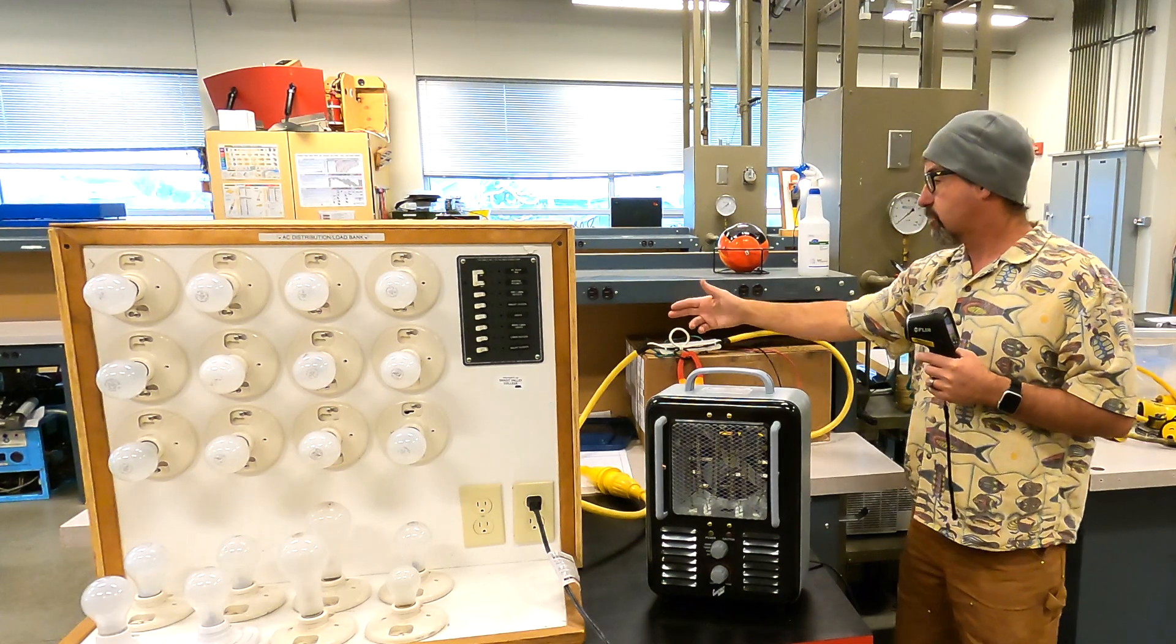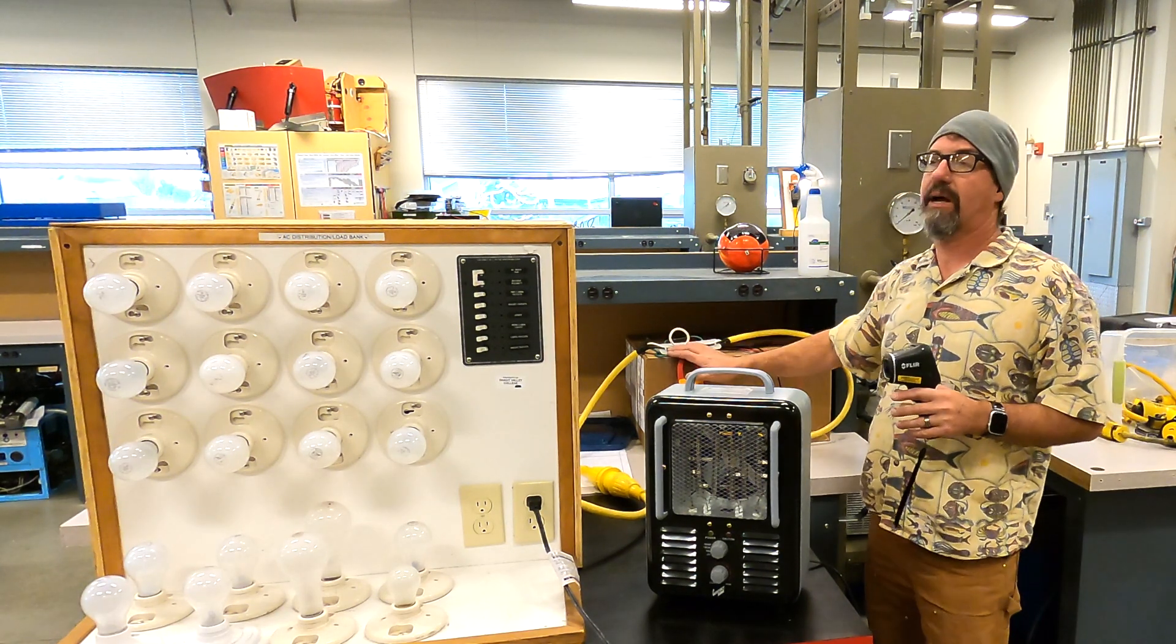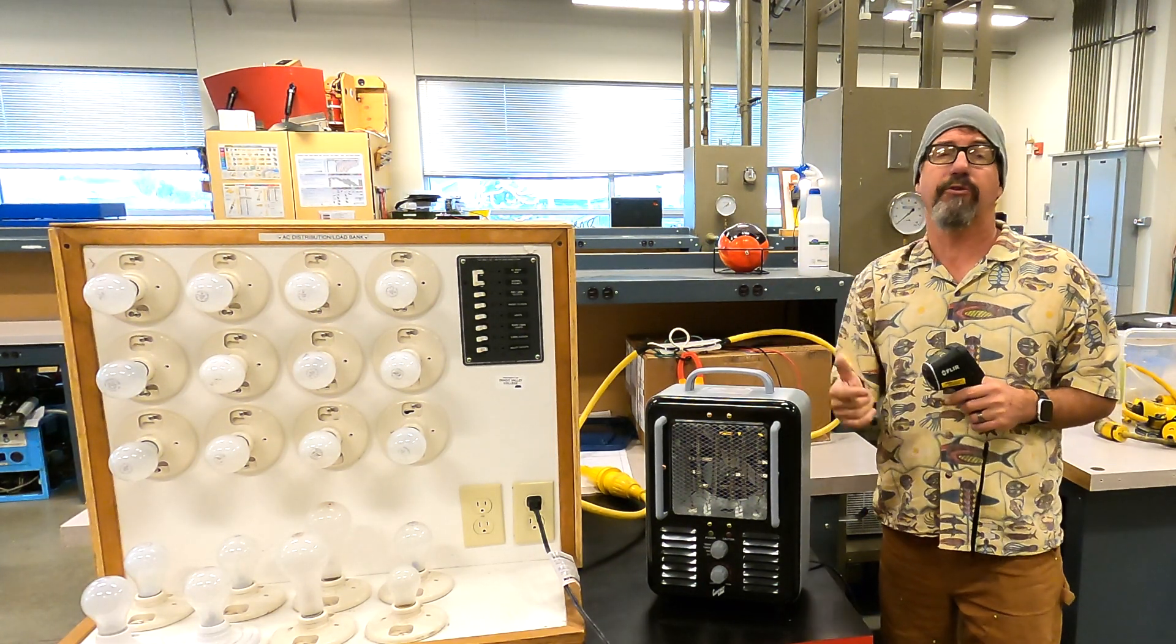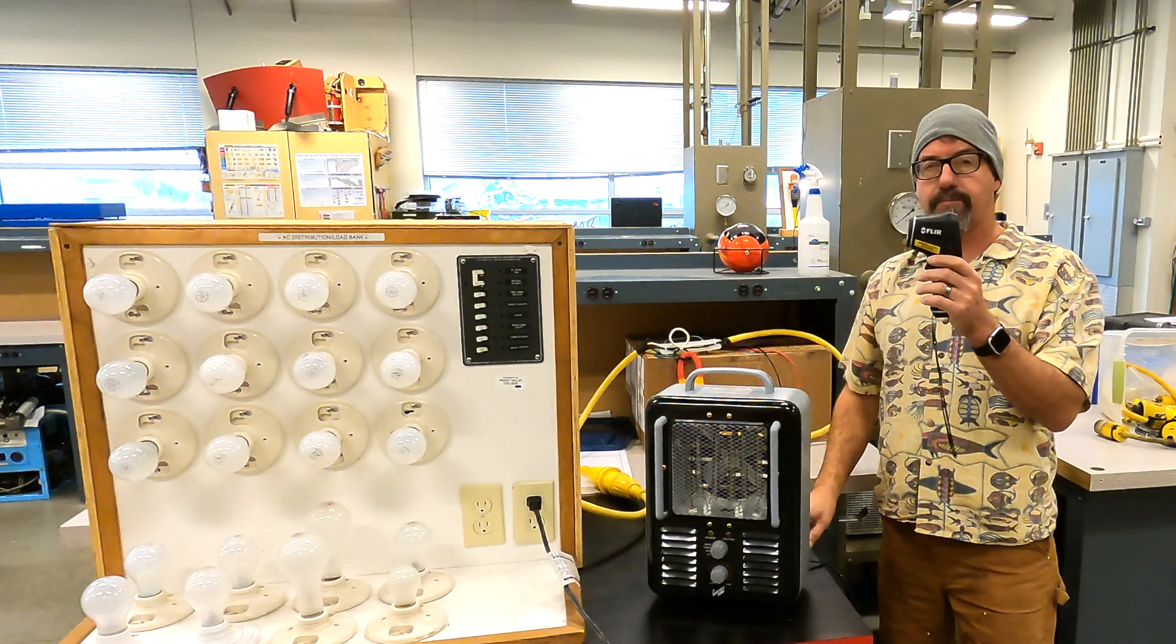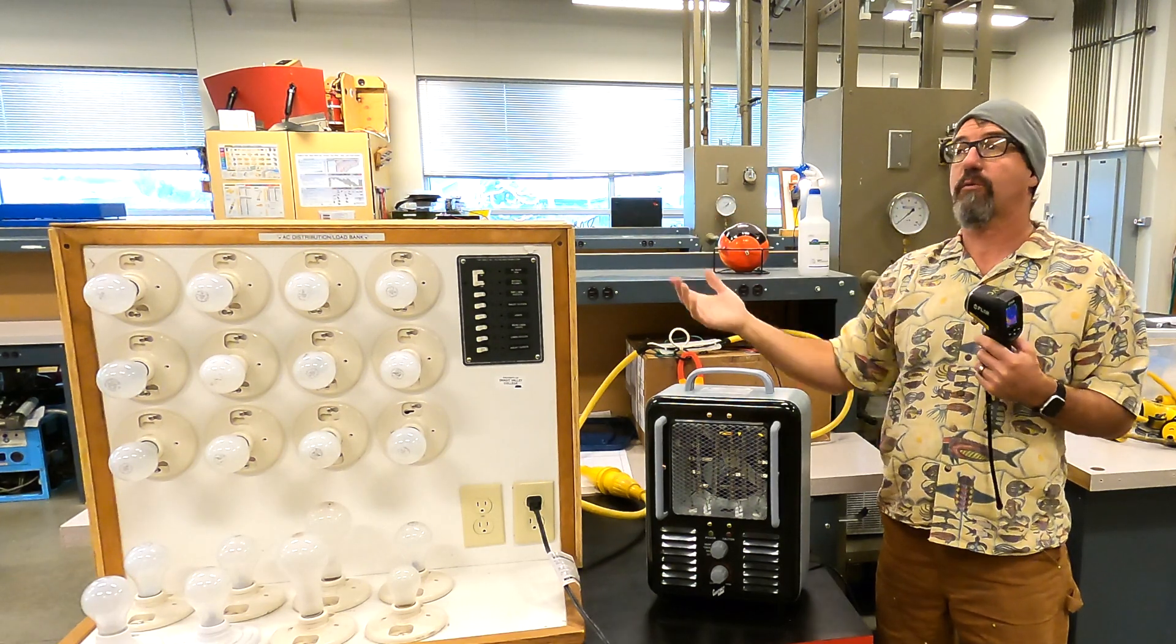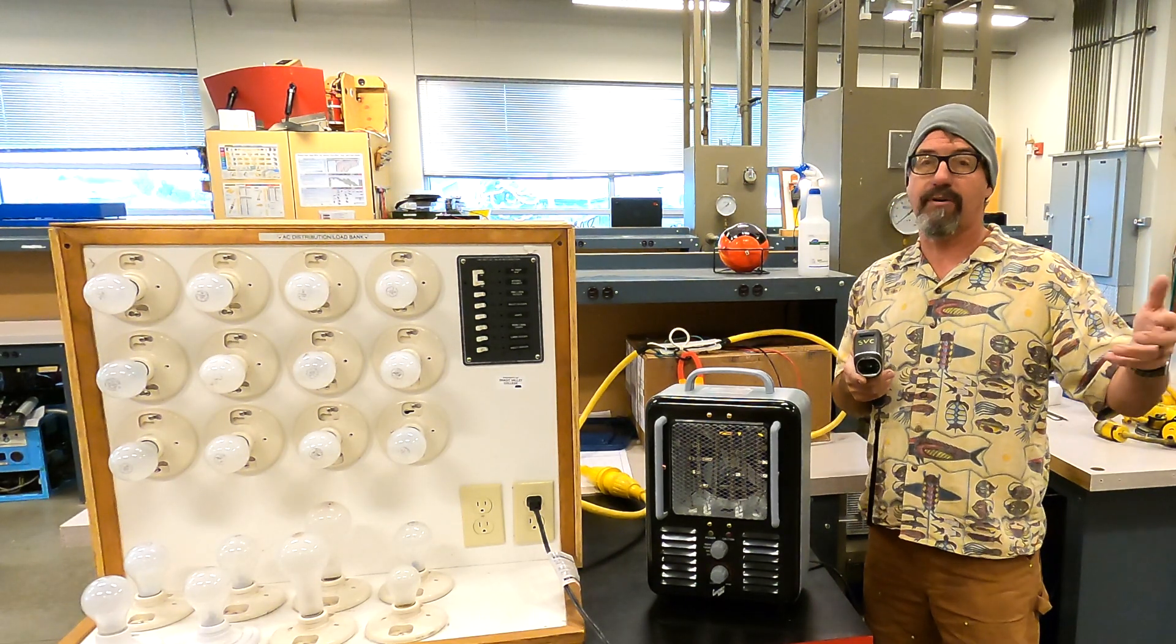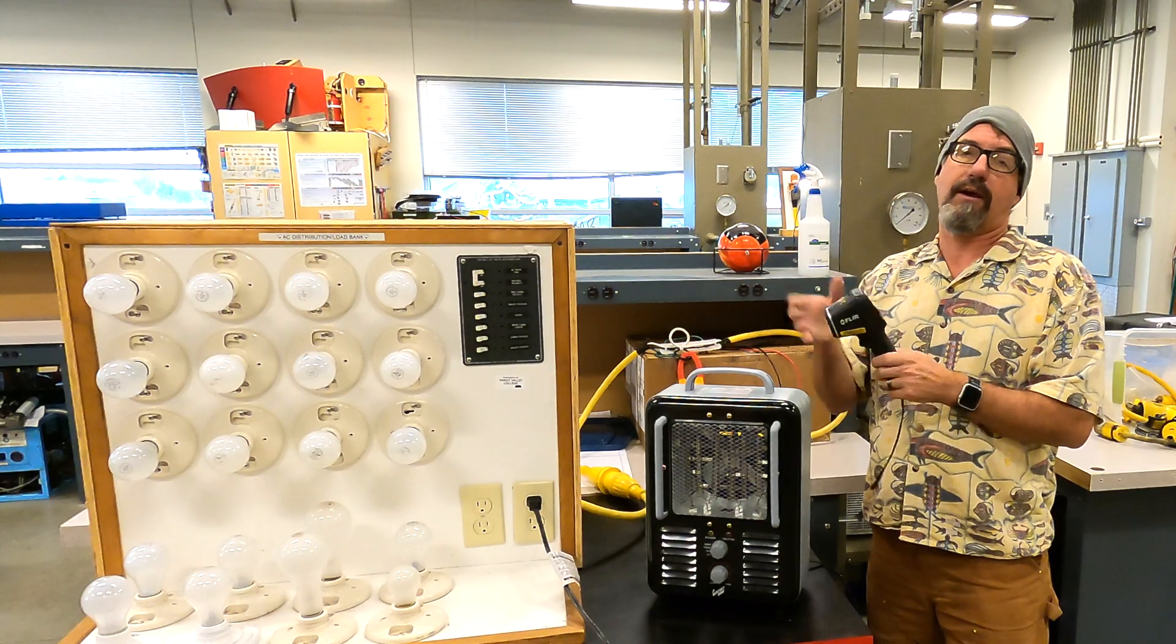Got to use good equipment. I've got a little split cord set up where I can tease out the black, white, and green to get just the hot wire to know what kind of amperage we're running. Electrical conductors when you pull energy through them naturally get a little bit warmer. That's why shore cords are rated 60 degrees C because they're outside of the boat. If you have cabling in an engine room, it's supposed to be 105 C. ABYC has got the tables to make sure we do that safely.